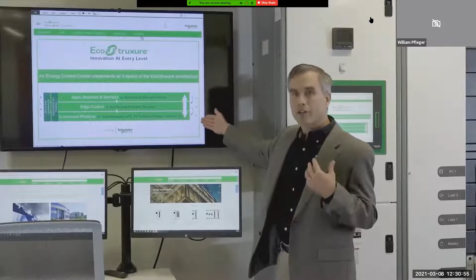Connected products tend to do a function very fast, in the millisecond time frame, and quite autonomously. For example, using the breaker, if there's a short circuit on the load downstream, the breaker is going to open in tens of milliseconds, and it doesn't need anybody's permission to do that. It's a breaker—that's what circuit breakers do.